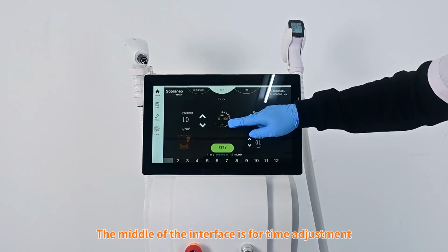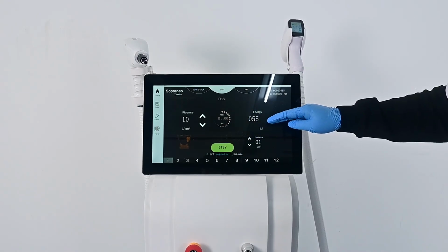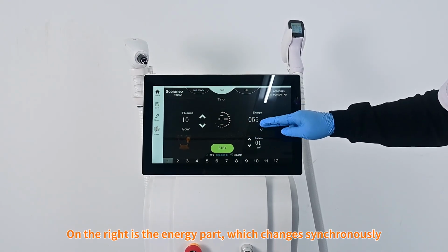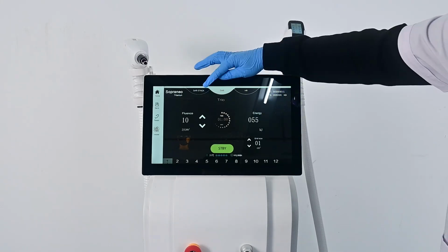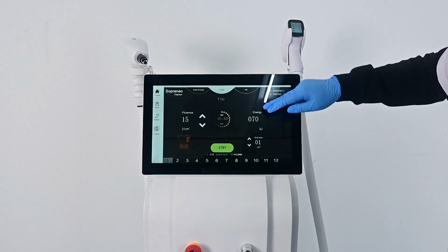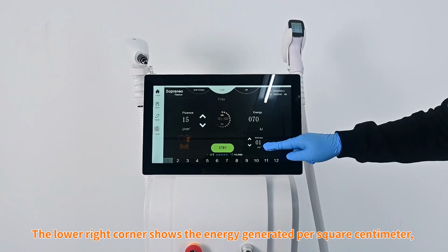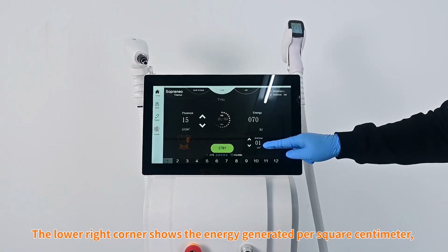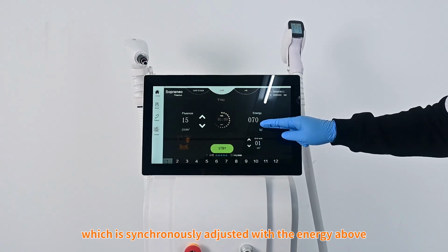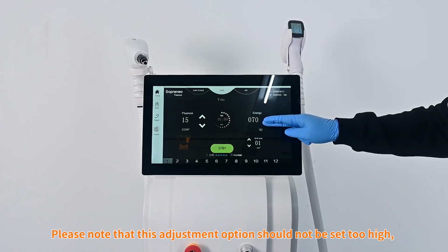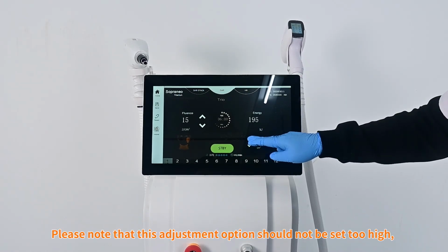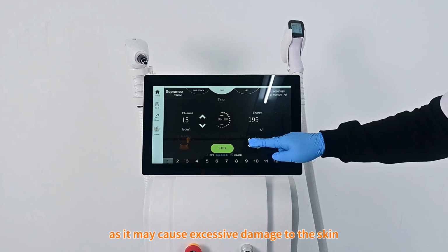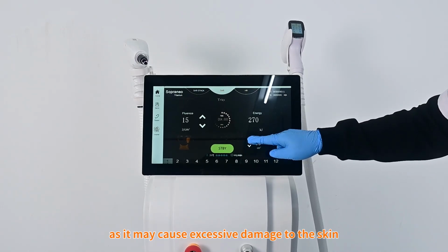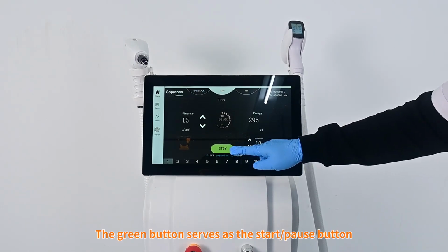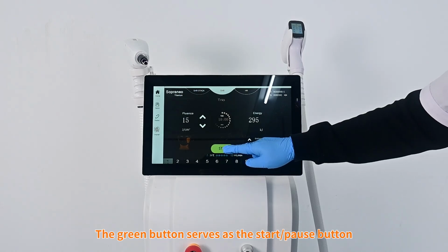The middle of the interface is for time adjustment. On the right is the energy part, which changes synchronously. The lower right corner shows the energy generated per square centimeter, which is synchronously adjusted with the energy above. Please note that this adjustment option should not be set too high, as it may cause excessive damage to the skin. The green button serves as the Start Pause button.